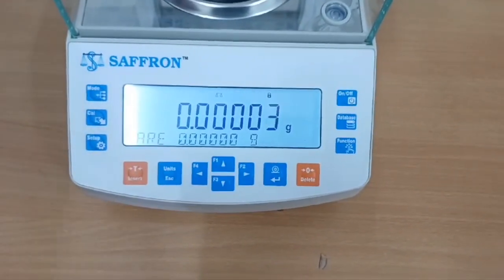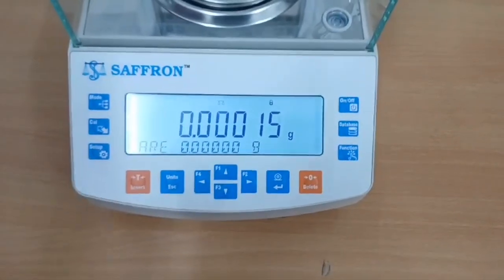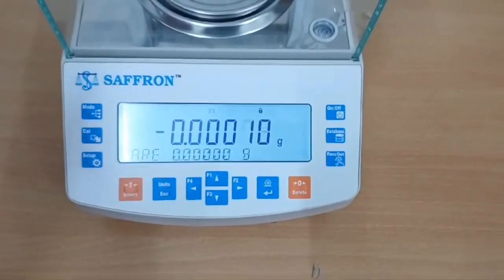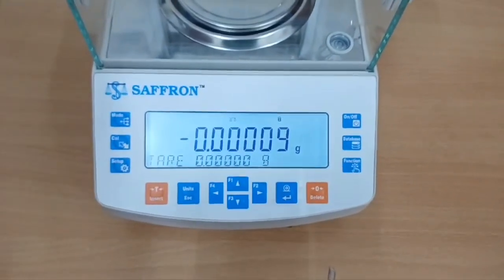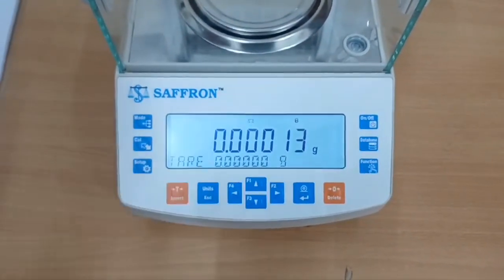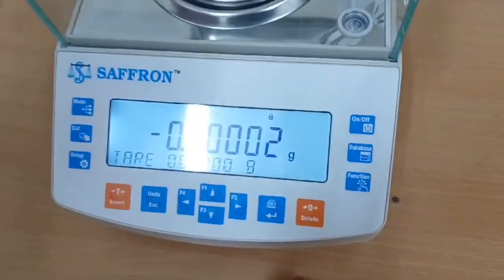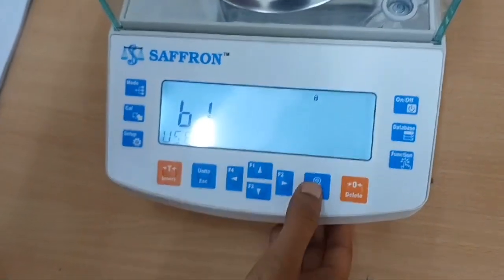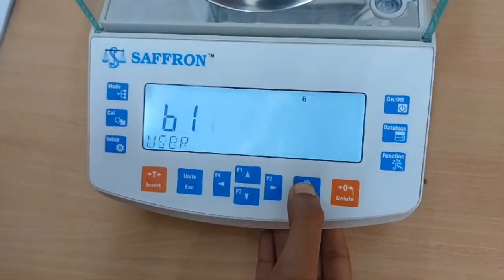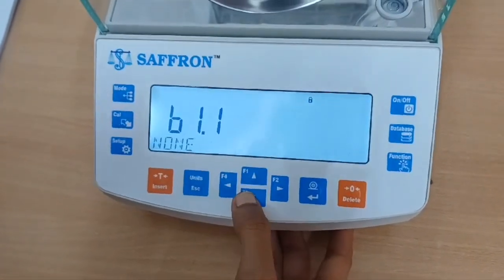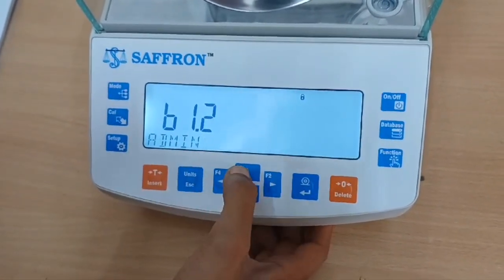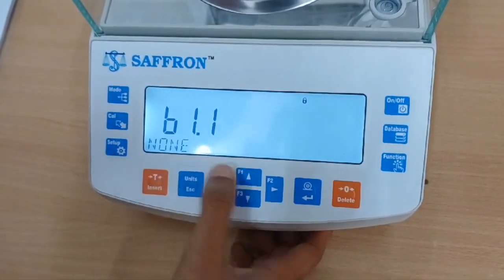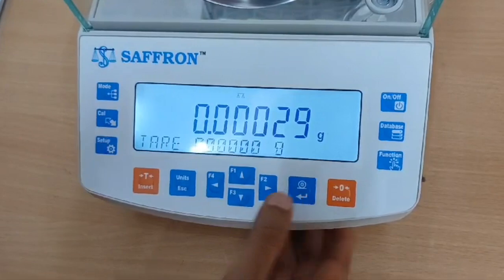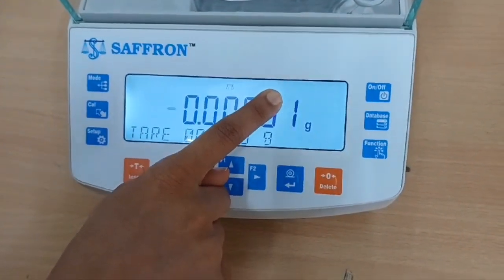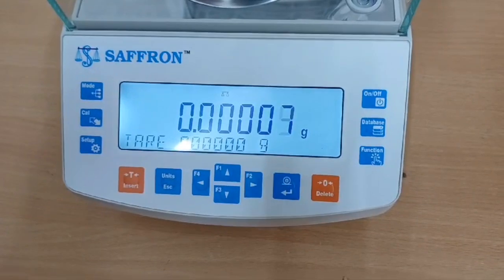The second use is if you have to change the settings of the device. This may be auto taring or language change, etc. In any other case, we don't recommend logging in. We'll now show you the logout procedure. So similar to the login procedure, we go to database and select user, and we click enter. Here, last time we selected admin to log in, but in order to log out, when you see the none option on the screen, you click enter. As you can see, the lock symbol has disappeared, and this means that you have been logged out.